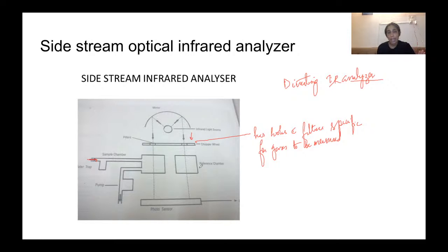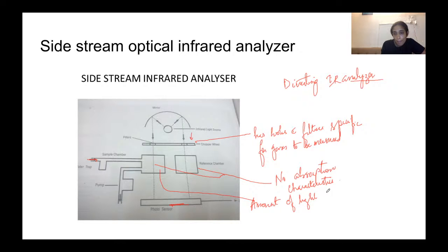Both these chambers have no absorption characteristics. From here your sample is coming, and from here the filtered infrared light is coming, passing through the reference chamber as well as the sample chamber. The light is then focused on an infrared photosensor. The amount of light absorbed by the sample gas is proportional to the partial pressures of the gases whose infrared light absorption is being measured. Basically, the amount of infrared light absorbed by the sample is directly proportional.